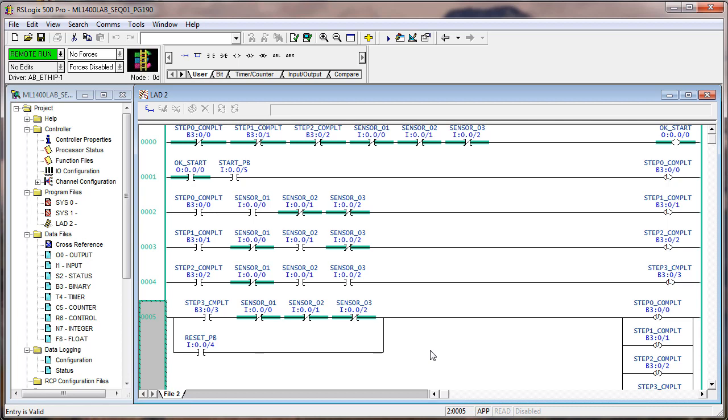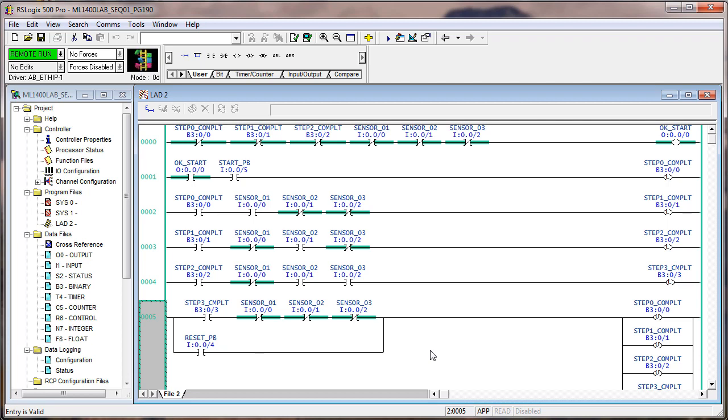This is real simple logic. Keep in mind that in the real world, these bits B3:0, B3:1, B3:2, and B3:3, the step zero, step one, step two, step three complete, those bits would probably be used to energize outputs that energize field devices, output field devices that cause motion or some sort of activity in the process, and the sensors respond. So right now if we hit the start push button, it's waiting for sensor one. So in other words, B3:0, step zero complete. Let's say that we use that bit to turn on some sort of an output, and that output moves something until sensor one sensed the position.